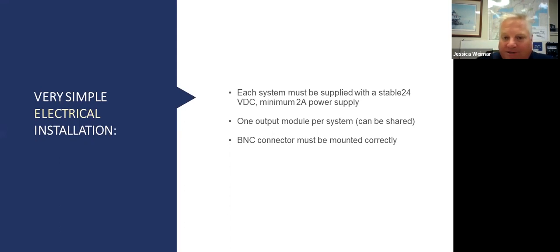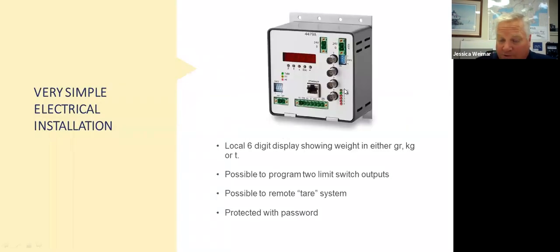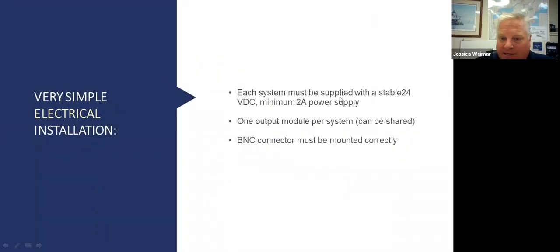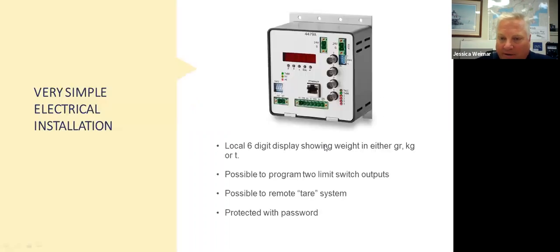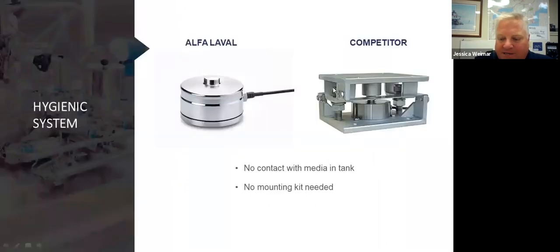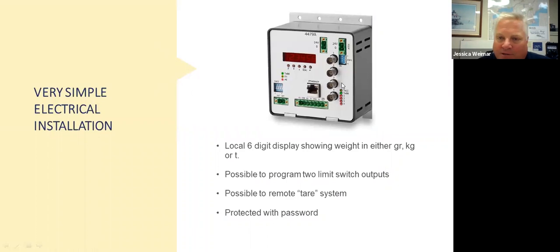And again, these are some considerations. You need the output module, which is that weighing module. You need one of those per system. And you've got to be sure that the BNC connectors are mounted correctly on your wiring. This is just an example of a different weighing module with 4 inputs. This particular weighing module can be used without a display if you want to integrate this directly into a PLC. You can do that and not require a display. You lose some functionality of the system, but OEMs sometimes use this because it's a little more cost competitive.